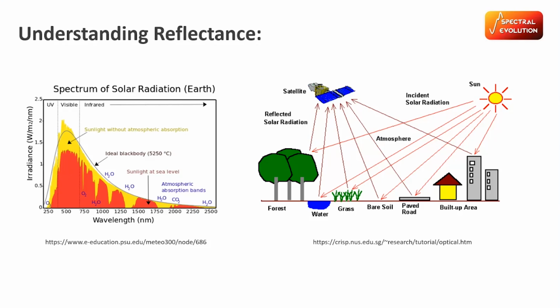If you're taking outdoor measurements, on the left we have a black body curve. When you're using the sun as an illuminator or your energy source, you're going to have two water bands where the atmosphere is absorbing 100% of your signal, so you're going to end up with noise there. Being able to deploy a field instrument that has its own internal light source is good if you're looking for a feature in those ranges, because it can target it with its own light source as well. On the right, we're just showing that a lot of these satellite or drone images are going to be very optically complex, and being able to decompose those with data from the ground is an important feature.